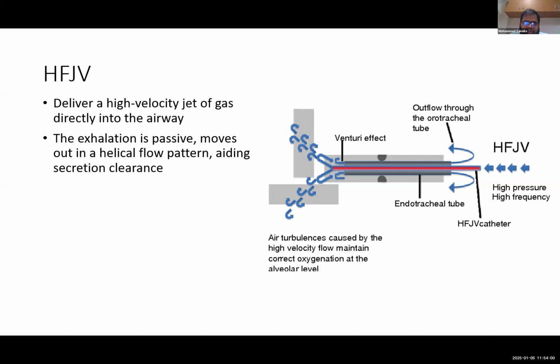The basic difference between high frequency oscillatory ventilation and jet ventilation is that in jet ventilation you are using a high velocity jet of gas, pushing it directly into the airway, at high pressure and high frequency. Similar to high frequency oscillatory ventilation, the tidal volume delivered will be low, and you are using a very high frequency, but not as high. In high frequency oscillatory ventilation you are using around 600 to 900 or 1000 sometimes, but in high frequency jet ventilation you will use around 300 to 500 respiratory rate.